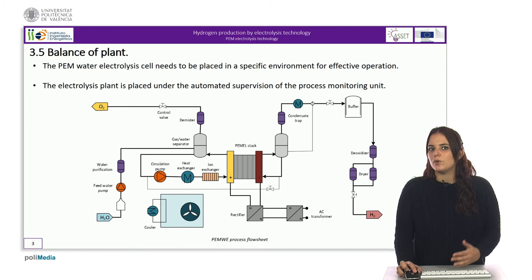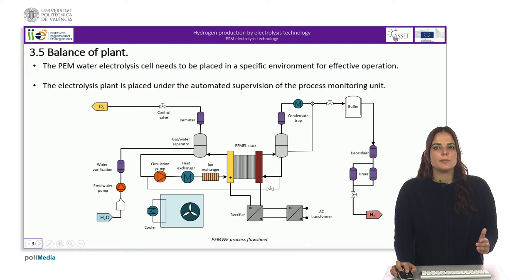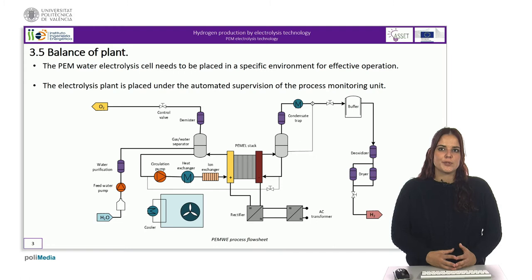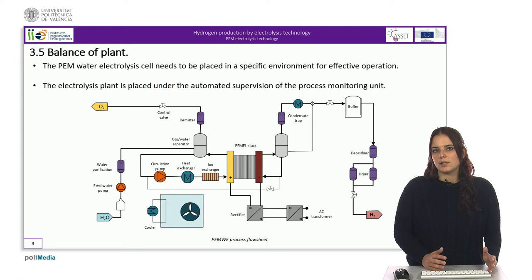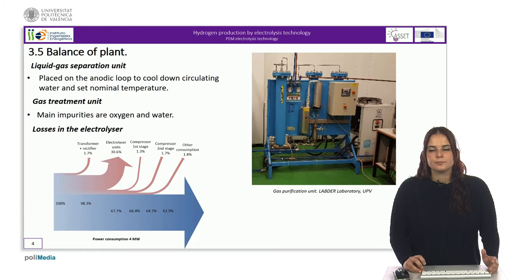Besides that, hydrogen is released after conditioning in an oxygen purifier and water dryer units that form part of the gas conditioning unit. The electrolysis plant is placed under the automated supervision of the process monitoring unit for continuous operation and monitoring. In a PEM water electrolysis plant, there is usually no thermostat to adjust the temperature of circulating water. The plant is designed to operate at nominal current density and the heat produced is extracted and dissipated to the surroundings via a blower. Heat dissipation is usually the rate-determining step that dictates the maximum operating current density of the electrolysis unit.